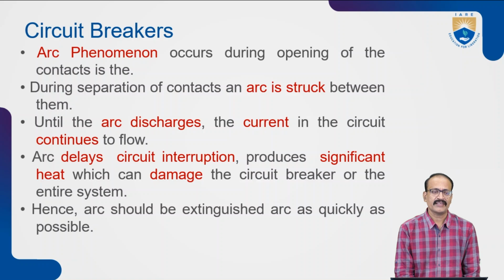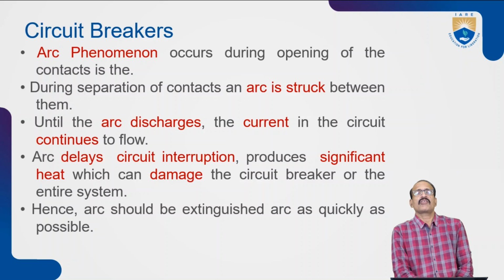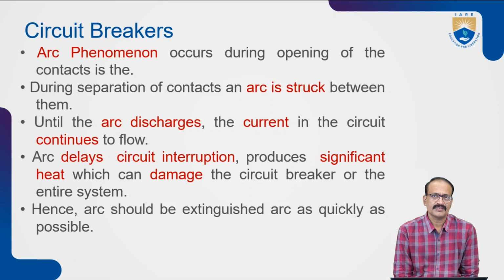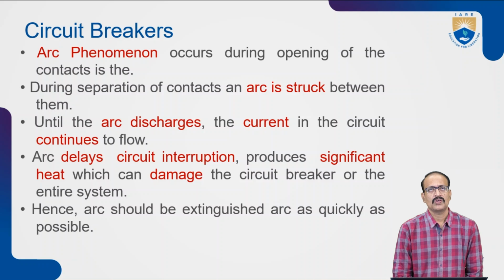During separation of contacts, an arc is struck between the contacts. Until the arc discharges, the current continues to flow. The arc delays the circuit interruption, that means circuit breaking, and produces significant heat which can damage the circuit breaker or the system, the power system protection system. So we have to extinguish the arc as early as possible.